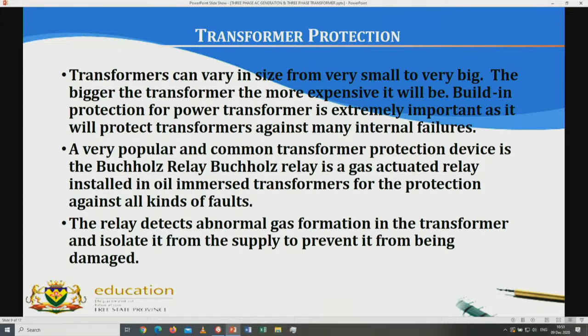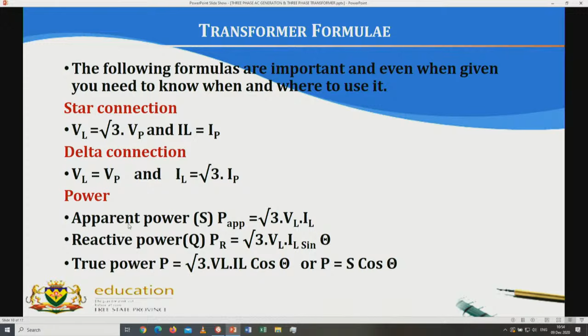Check. Under three-phase AC generation, I was talking about star connection and delta connection. Even under a three-phase transformer, I'm also talking about star connection and delta connection. In star, V line is equal to square root of 3 times V phase, and I line is equal to I phase. Under a delta connection, V line is equal to V phase, and I line is equal to square root of 3 times I phase. They are formulas of apparent power, reactive power, and true power.